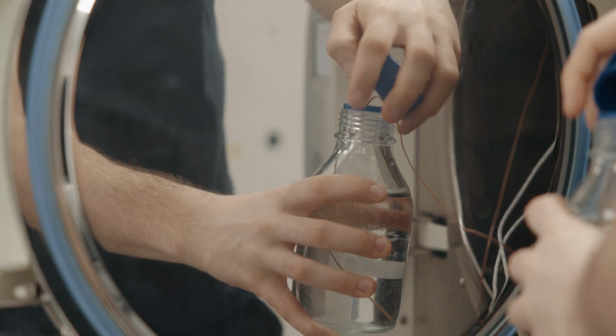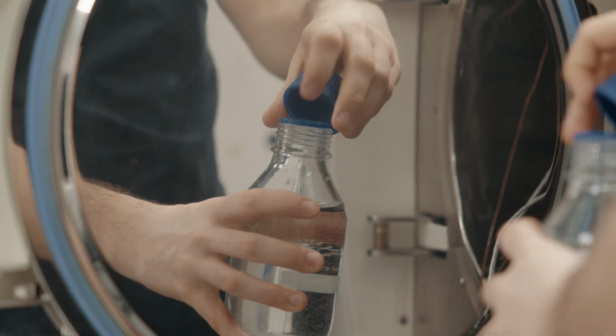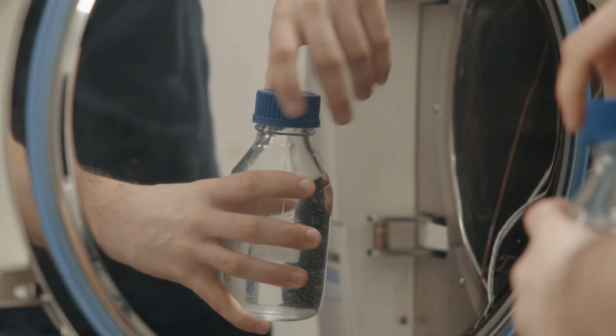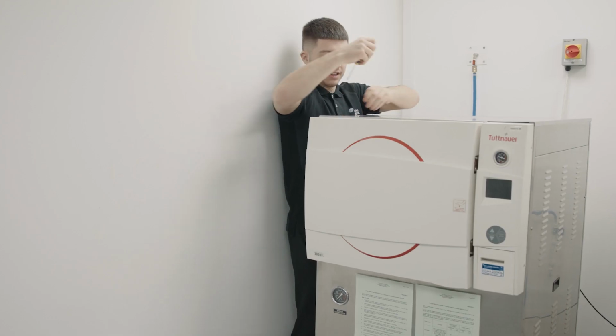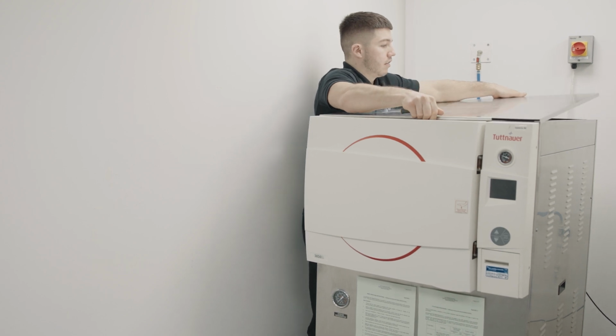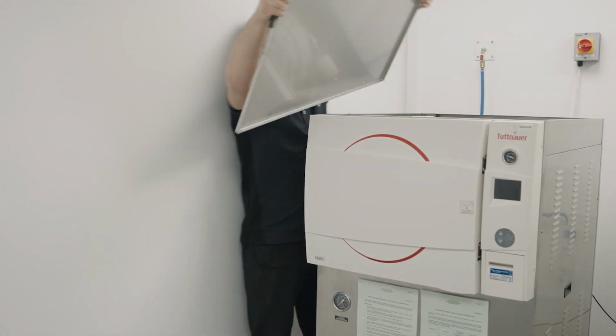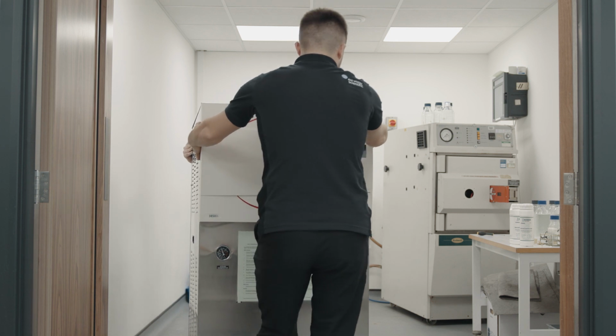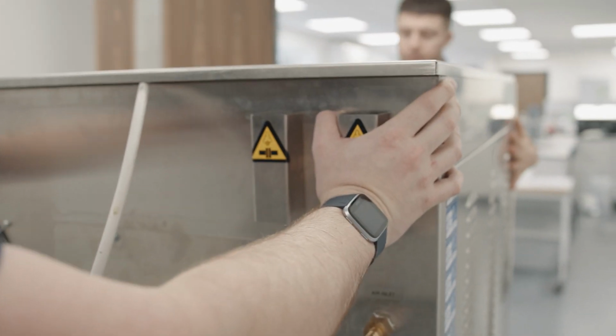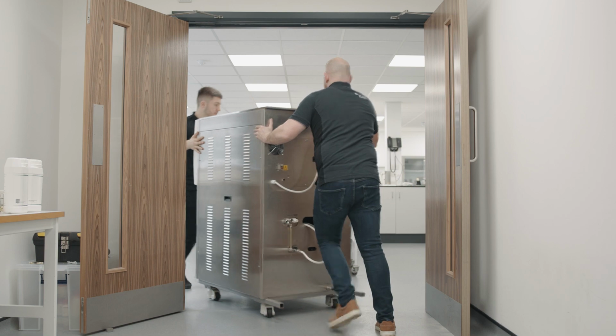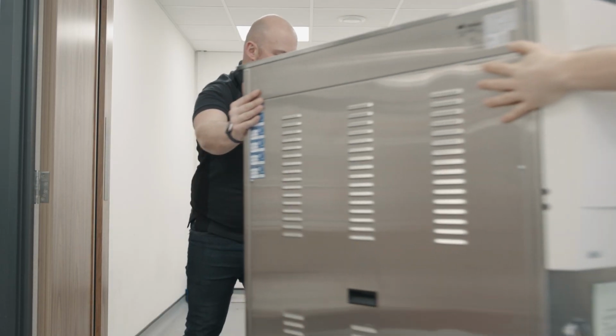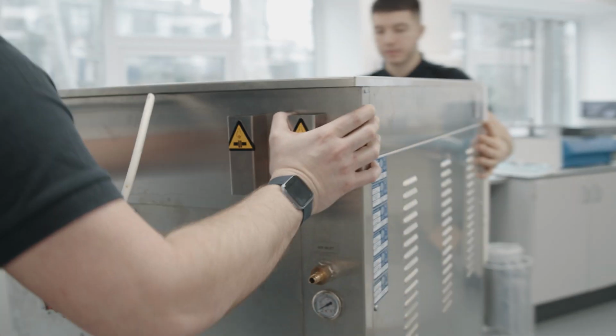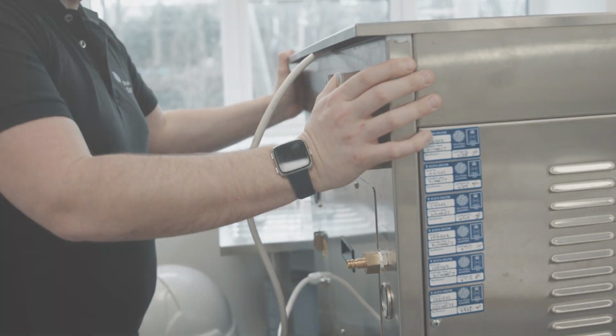It is recommended that validation be carried out as a result of a new program being set up to autoclave a previously unvalidated load, a change to the previously validated cycle, i.e. change to temperature or time requirements, a change to the load previously validated, i.e. the number of bottles being autoclaved, or a change in the size of the containers, extensive maintenance, or bringing an autoclave back into service after a period of inactivity, or where an autoclave has been relocated.